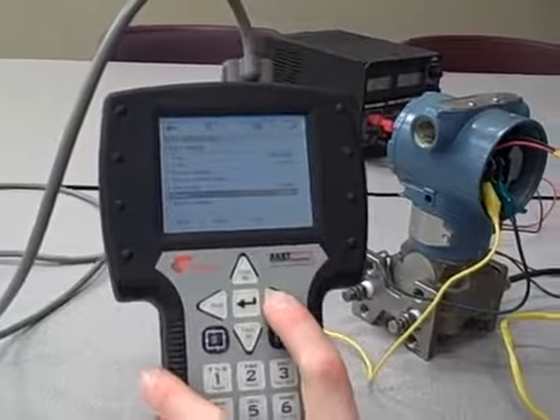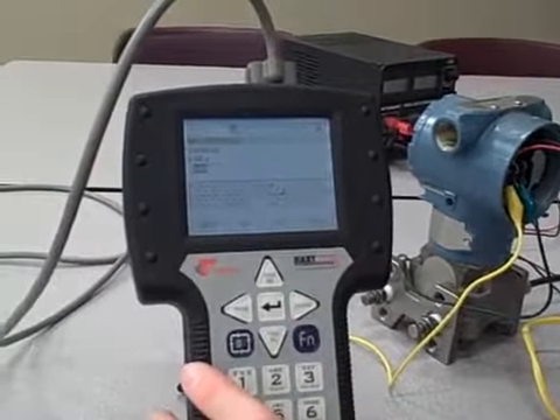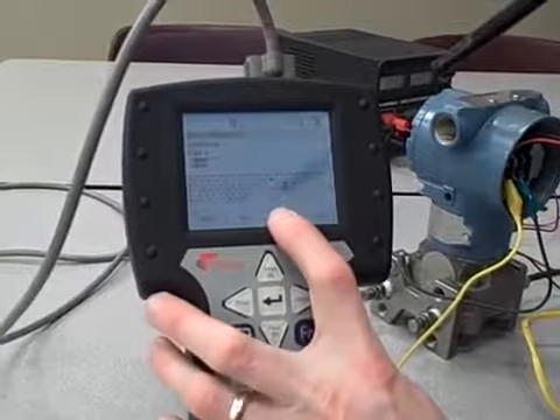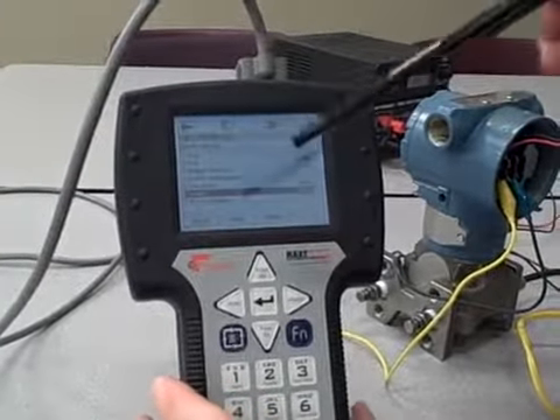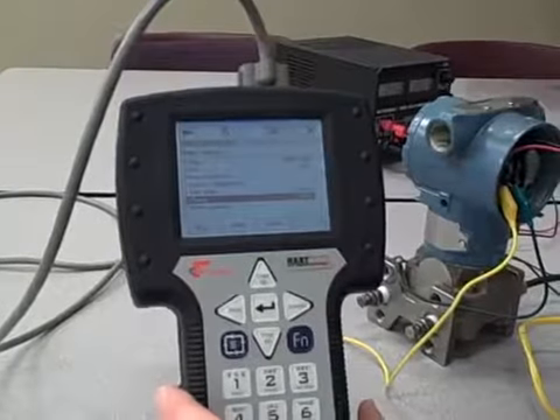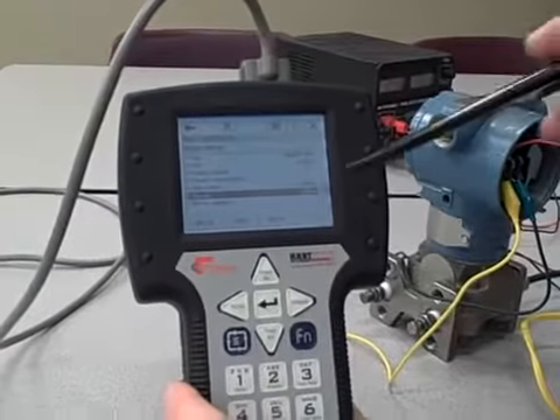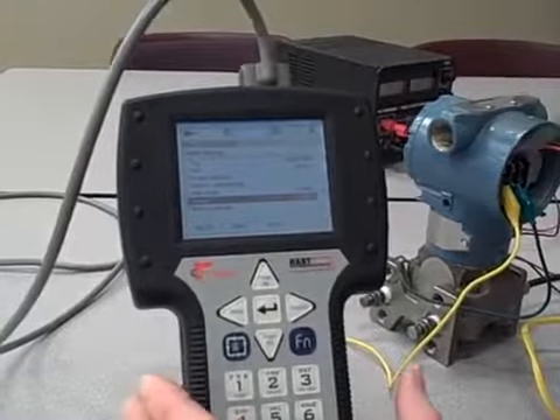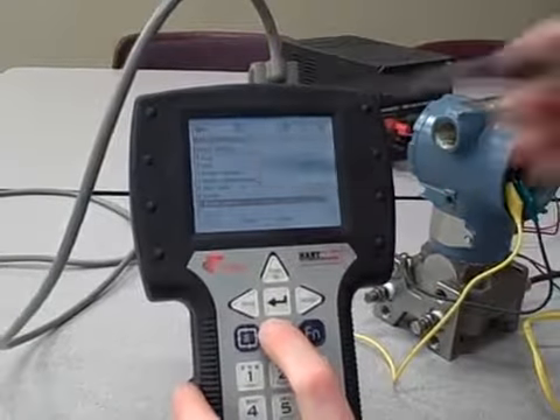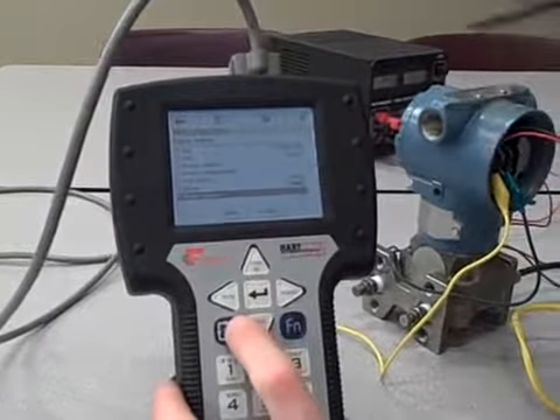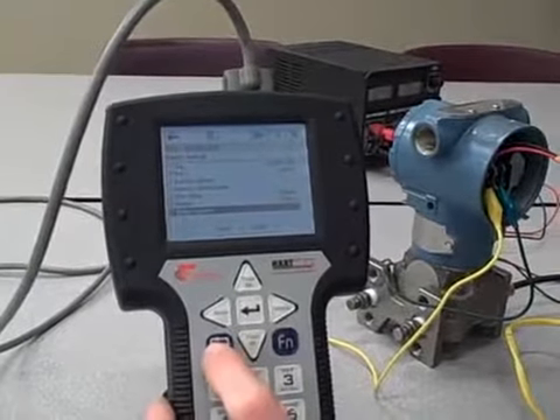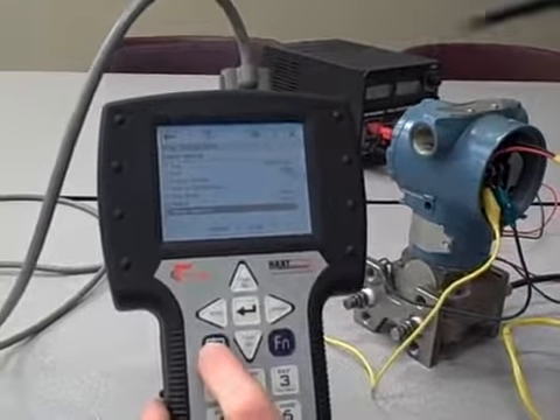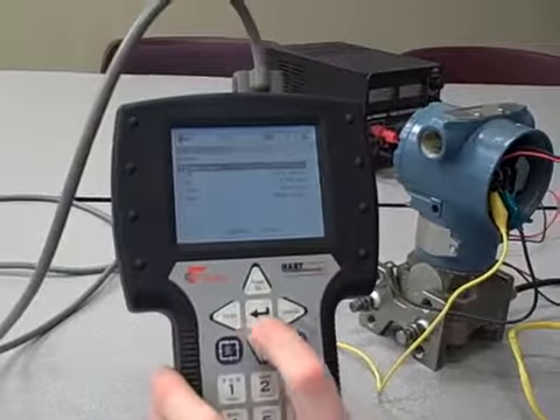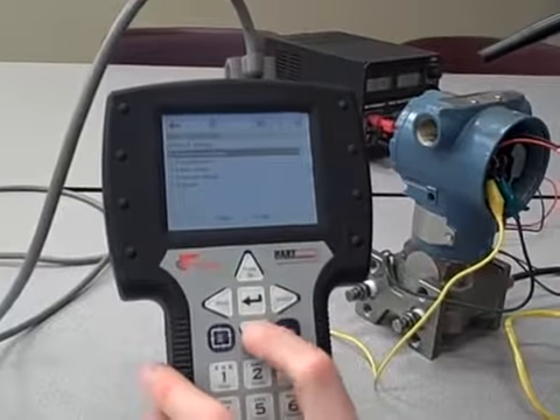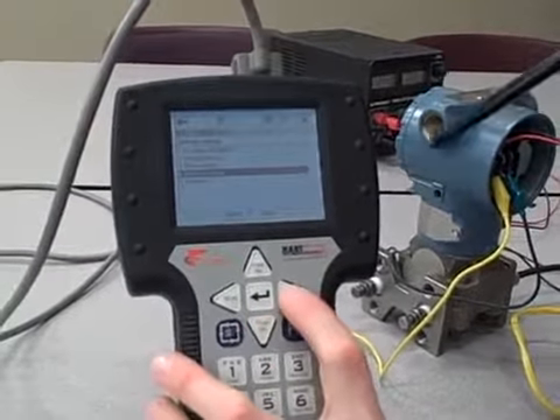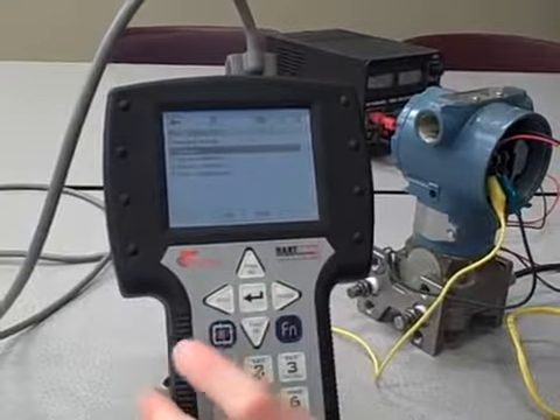We also have damping. Damping is essentially a low-pass filter function where we tell the transmitter to ignore or to dampen any fluctuating pressures that it sees. That's helpful when you're measuring a pressure that is noisy by nature. And then we have an option here called meter options. In case your transmitter has a built-in indicator on the side, you can set some various options that the indicator can follow. Going back to the device setup menu, we also have detailed setup in case basic setup wasn't detailed enough.